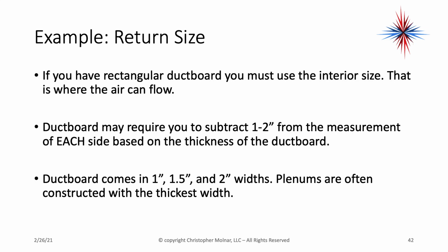If you have rectangular ductwork, you must use the interior size. That is where the air can flow. Ductboard can require you to subtract between 1 and 2 inches from the measurement of each side based on the thickness of the ductboard. Ductboard comes in 1 inch, 1.5 inch, and 2 inch widths. Plenums are often constructed with the thickest width.